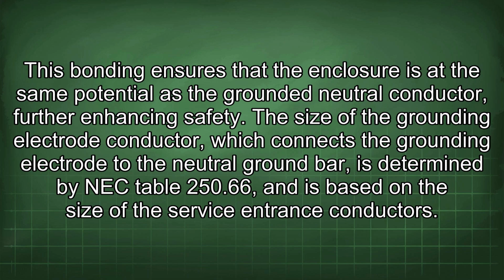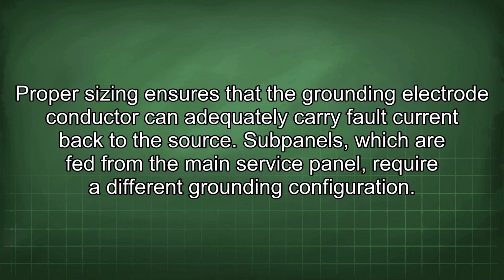The size of the grounding electrode conductor, which connects the grounding electrode to the neutral ground bar, is determined by NEC Table 250.66 and is based on the size of the service entrance conductors. Proper sizing ensures that the grounding electrode conductor can adequately carry fault current back to the source.